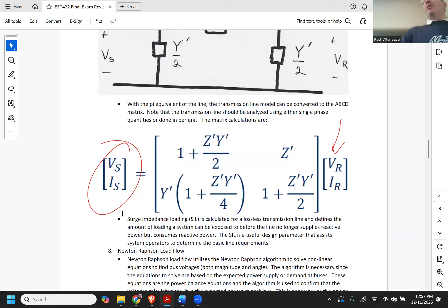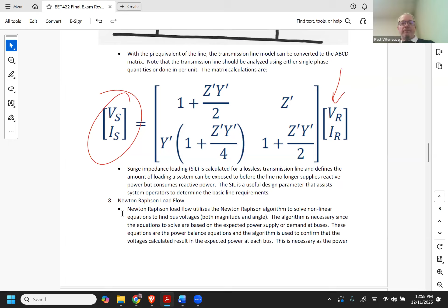The last thing we talked about for transmission lines is surge impedance loading. If you have a lossless transmission line, you can estimate approximately what the surge impedance loading is and when the line starts to consume or absorb VARs. As long as your X over R ratios are fairly high, 30 or 40 or greater, you can go ahead and use that surge impedance loading concept and say this is valid. Other than that, you can't necessarily do it because it's not a lossless transmission line.